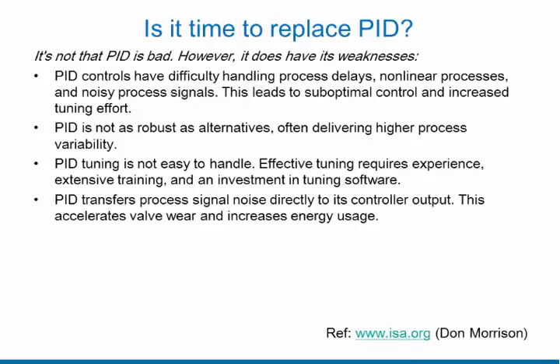When we look at the limitations of that type of controller, three main issues arise where PID feedback loops aren't exactly the best way. The biggest one is where the gain isn't linear. For instance, if we have a reaction where the process variable and the manipulated variable have a fairly linear and constant relationship all the way through.